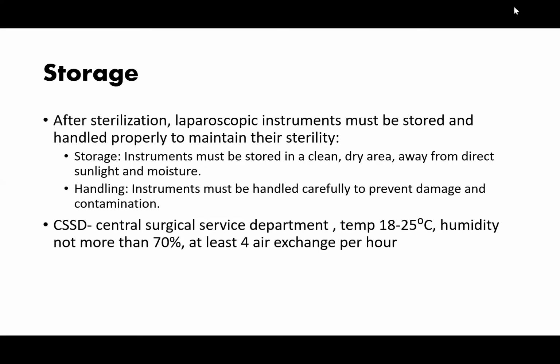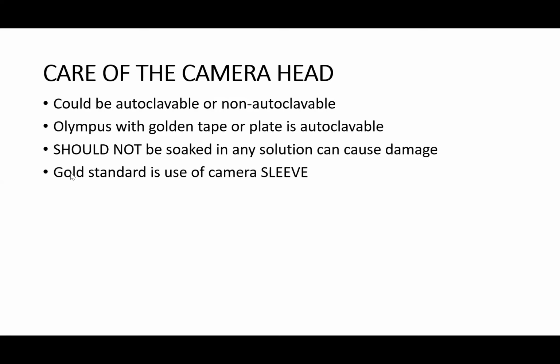Now, handling. Instruments must be handled carefully to prevent damage and contamination. Now, in the CSSD, Central Surgical Service Department, the ideal temperature is between 18 to 25 degrees Celsius and a humidity not more than 70%, and at least 4 air exchanges per hour. And of course, first come, first to leave. The instruments that are brought earlier are the ones to be taken out first, so that you don't have instruments staying for a very long time in the sterilization unit. Now, there are some specific instruments that need special handling, like the camera head.